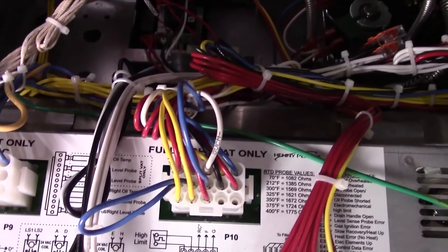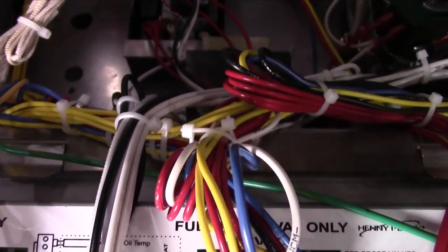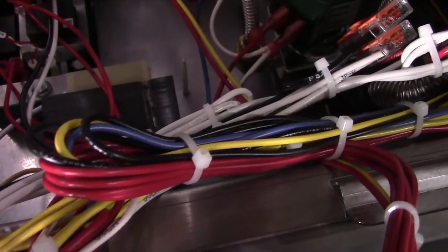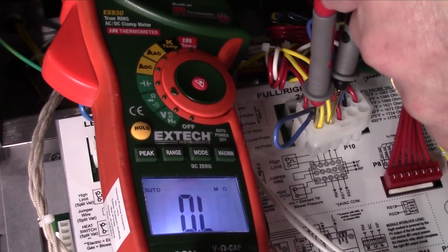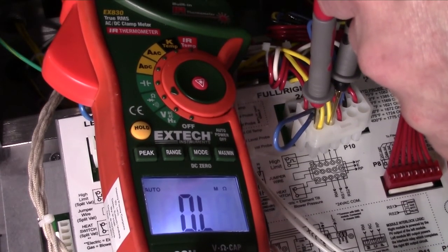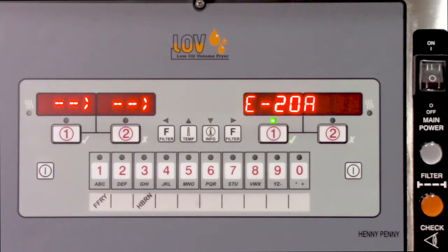If the switch tests open at the pressure switch but at the control it tests closed, then find the short in the wiring from the switch to the control and replace the bad section of wire. If, more uncommonly, the switch tests closed at the control but the control still displays an E20A, then replace the control panel.